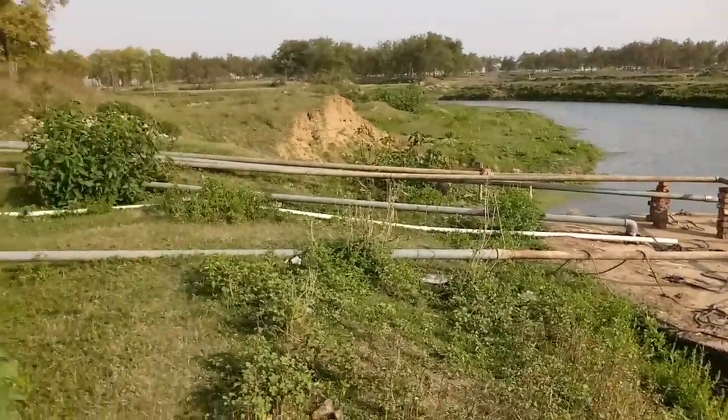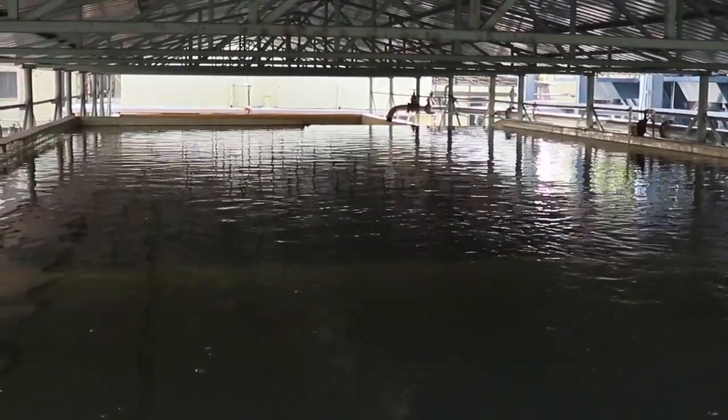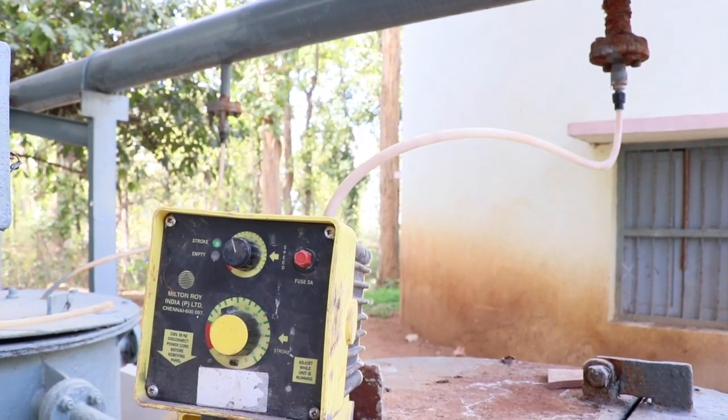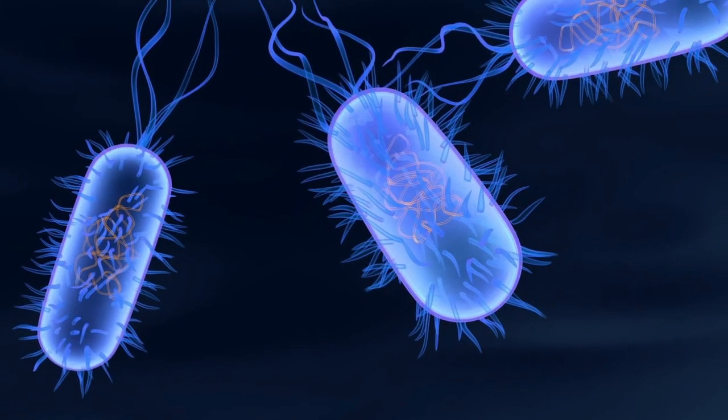So, what do we do? We withdraw the water from the river using several pumps operating around the clock. We draw the water and store it in large sumps — large reservoirs. From there, we take it for treatment. The first stage is pre-chlorination, where we add chlorine to kill any microorganisms already present. Since we have a large amount of organic matter, there are a lot of microorganisms, so we do not want all that to go into the treatment processes. Hence, we have this pre-chlorination step.